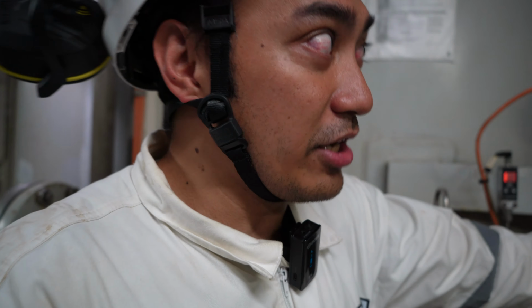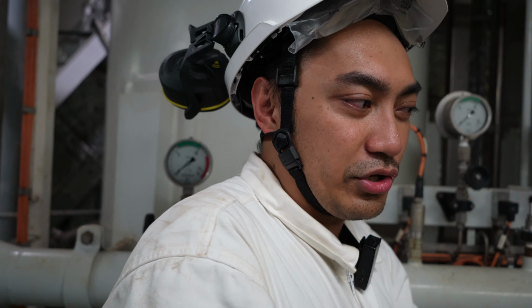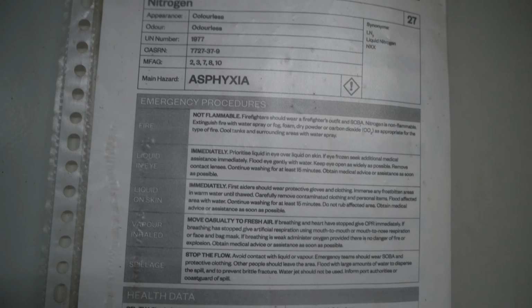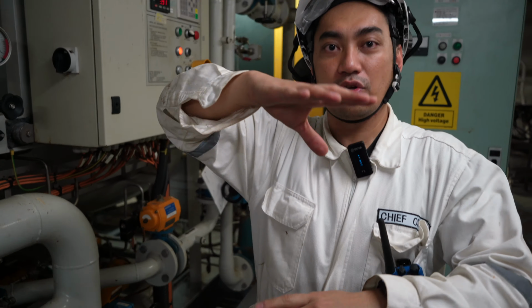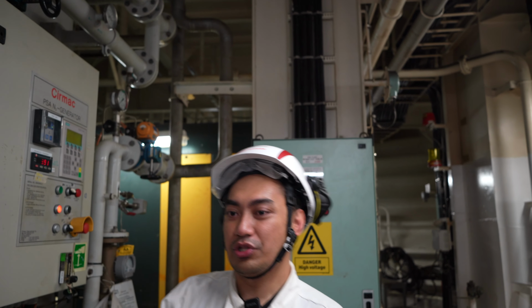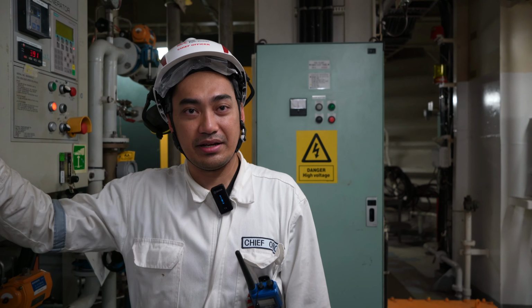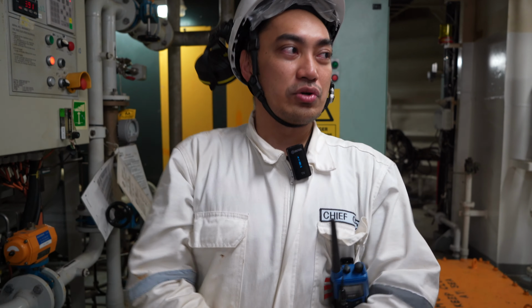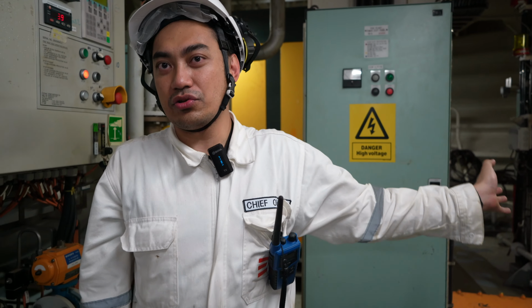Yes, carbon molecular sieve. These are carbon particles that are filled inside these tanks. Whenever dry air comes, these carbons attract the oxygen and retain it, so that pure nitrogen goes out into the outlet. So again, we do not permit anything above 6 degrees. Now, how do we reduce the dew point? We've already reduced it at some point in the dryer, but we have to further reduce it to be sure. That can be done through a bypass valve.